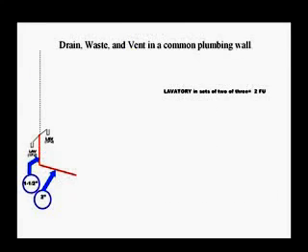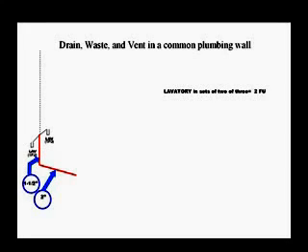Under Maximum Units Horizontal, 2 fixture units fits under 8 fixture units, which will require a 2 inch drain. Note the small number 3 for footnote number 3 at the bottom of the table. It reads, except 6 unit traps or water closets, which in this case will not apply. This section of the building drain is 1-1/2 inch for the vertical and 2 inches for the horizontal drain.